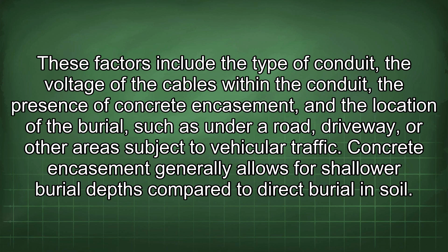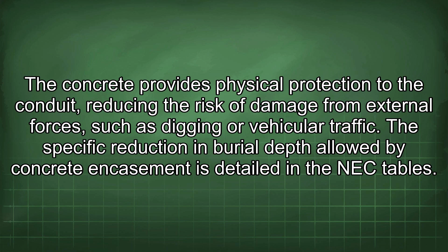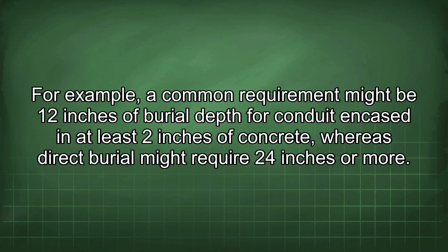Concrete encasement generally allows for shallower burial depths compared to direct burial in soil. The concrete provides physical protection to the conduit, reducing the risk of damage from external forces, such as digging or vehicular traffic. The specific reduction in burial depth allowed by concrete encasement is detailed in the NEC tables. For example, a common requirement might be 12 inches of burial depth for conduit encased in at least 2 inches of concrete, whereas direct burial might require 24 inches or more.